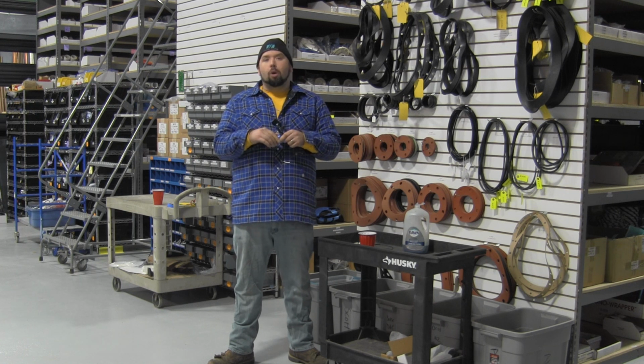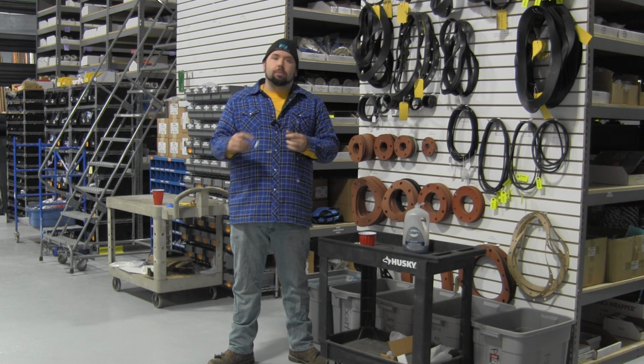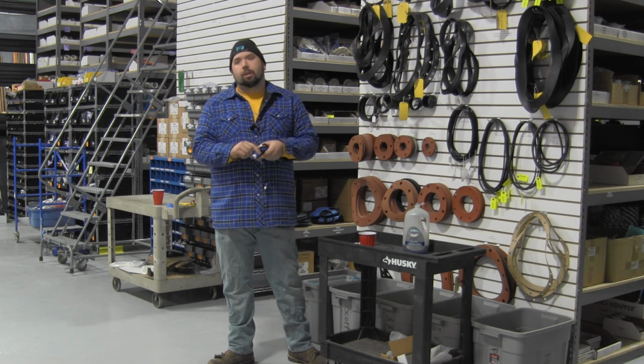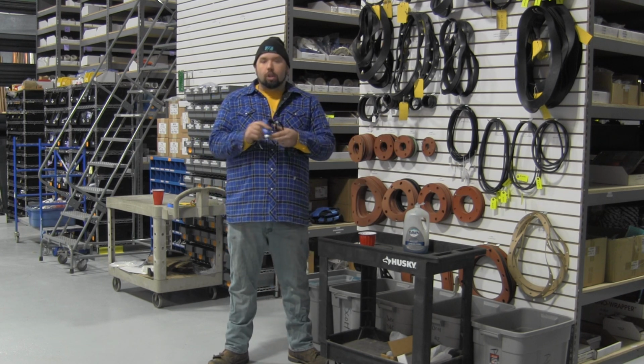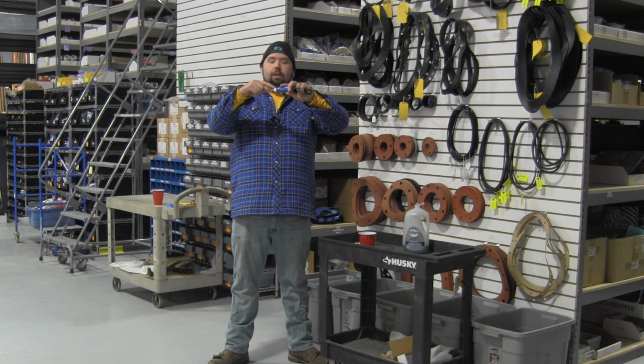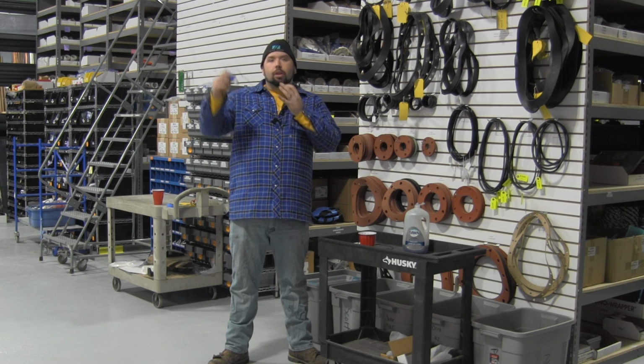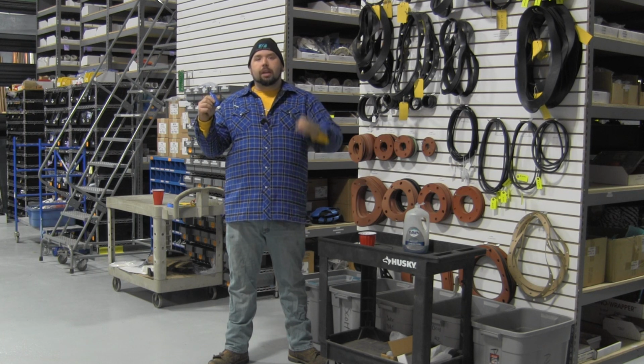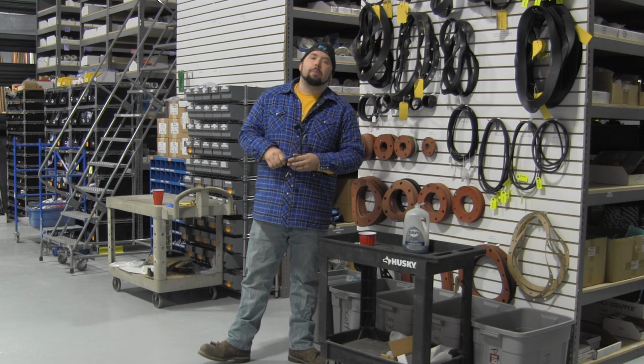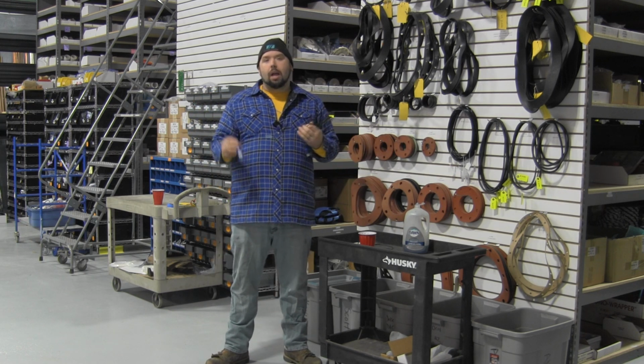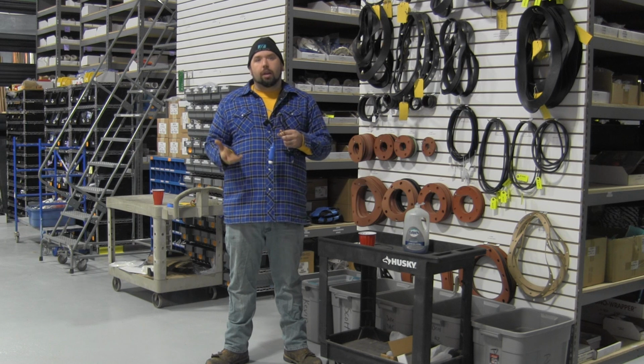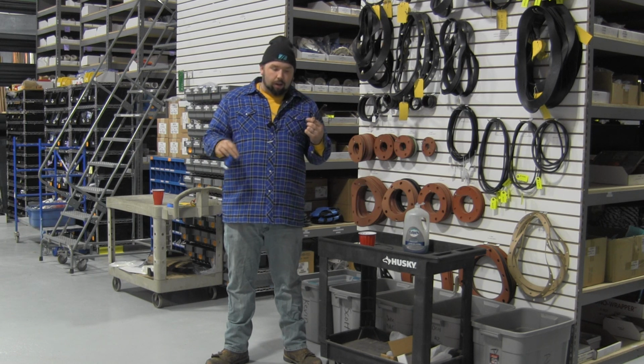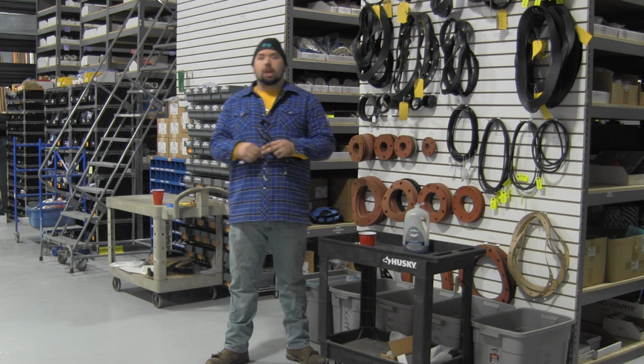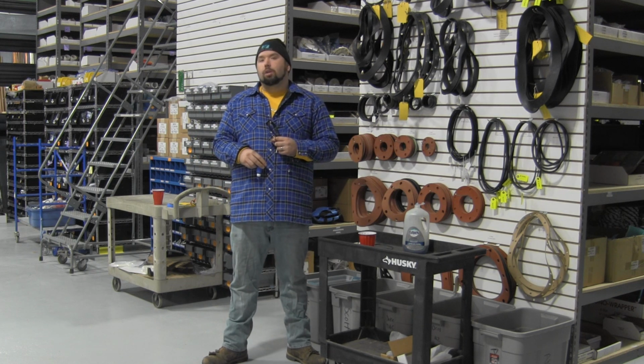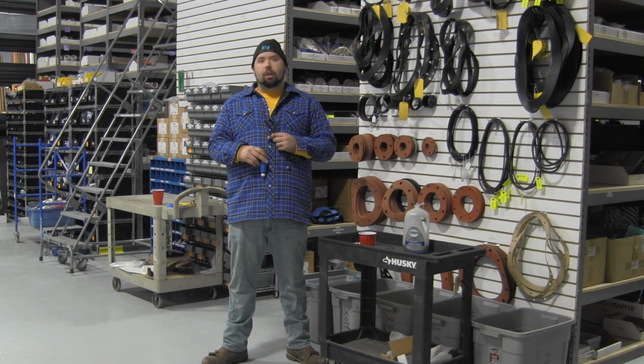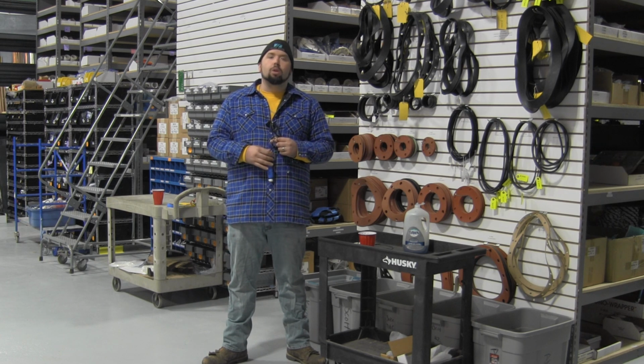But before you put the probe into the flow cell, you want to shake it down to be sure that the gel inside the probe is at the tip where it needs to be. All right. Once you've done that, you want to make sure you have sealant tape on the threads of the probe. Reinsert the probe into the flow cell. Reconnect your BNC connector. Leave your controller off for approximately 1 to 2 hours. Let the probe acclimate to the water and settle down. If you do not let the probe adjust to what's in the water, your controller will be all over the place, and you will find that you will overfeed or underfeed chemicals into the pool, and you will have nothing but issues.